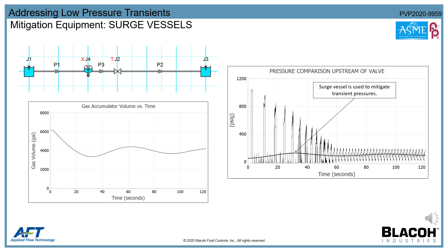The second most common method for mitigating low pressure transients is through the use of a surge vessel. Surge vessels have advantages in that they allow the system to remain closed and can mitigate high pressure transients as well. In the cavitation example, the surge vessel attenuates the high pressure transient wave, and as the flow reverses, it sends fluid into the piping, preventing the system from going into a vacuum state.